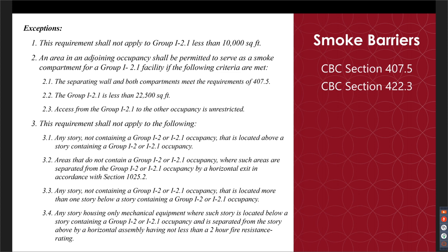And then there are additional exceptions that they don't need the smoke compartment, the smoke barrier. If any story not containing an I-2 or 2-1 that is located above a story containing an I-2 or 2-1, because if you think about relocating, if you're on the I-2-1 story, we're not going to take them up in a fire, right? That's bad. Fire goes up too. So they don't need to go up for relocating. For areas that do not contain the I-2 or 2-1, where such areas are separated from the I-2 or 2-1 by a horizontal exit. So if they have that horizontal exit separating those areas, they don't need that other smoke compartment, smoke barrier. If there's a story that is located more than one story below a story containing I-2 or 2-1, they don't need that smoke compartment there, because if you're at the point where you're relocating 2 stories down, it's pretty bad, probably time to get out. And then if there's any story housing only mechanical equipment, they don't need that smoke compartment as long as there's a 2-hour separation, because we don't like to relocate our occupants to mechanical floors.